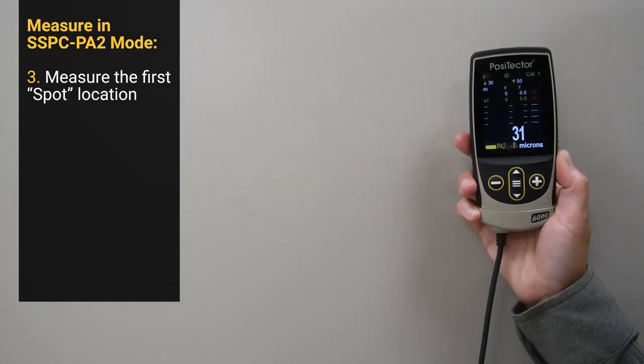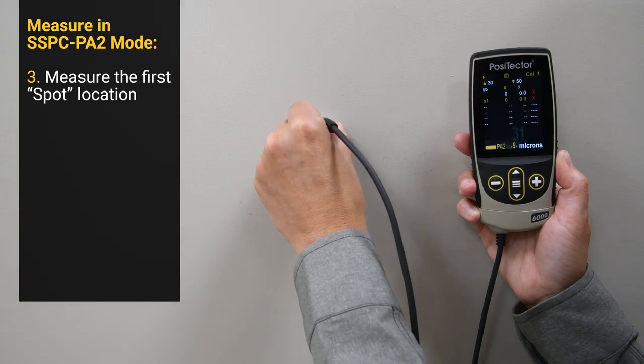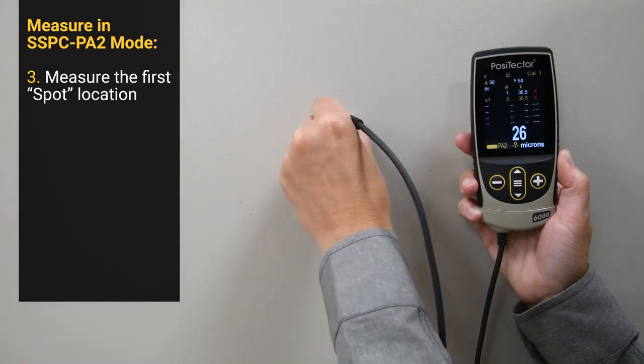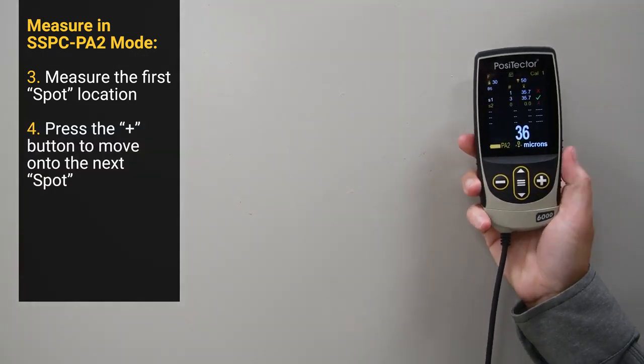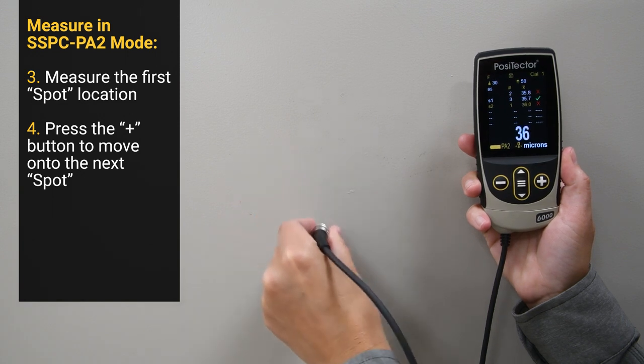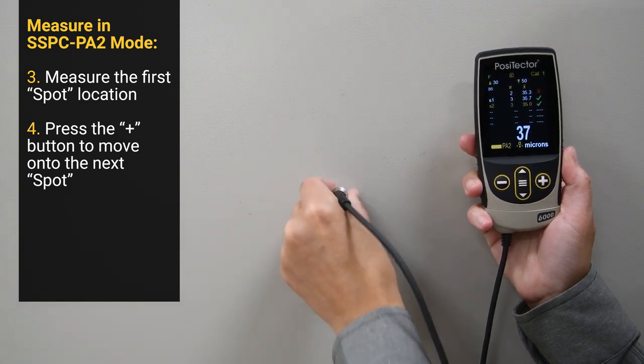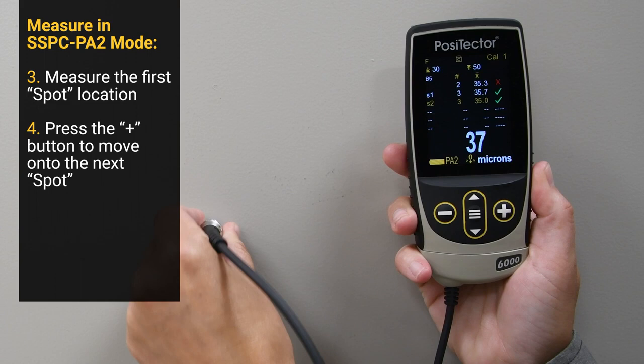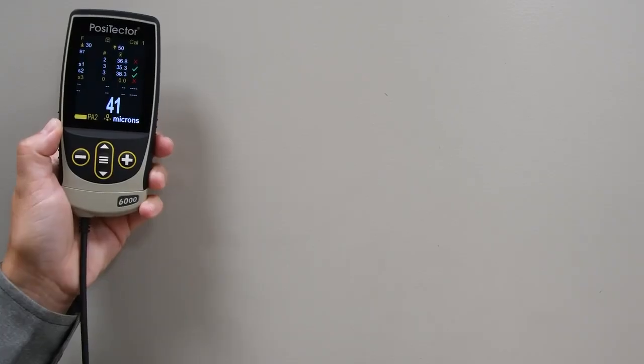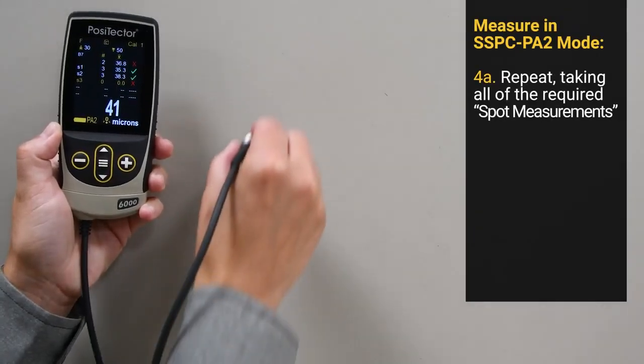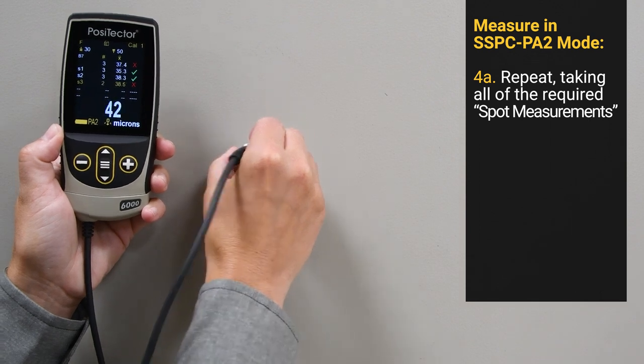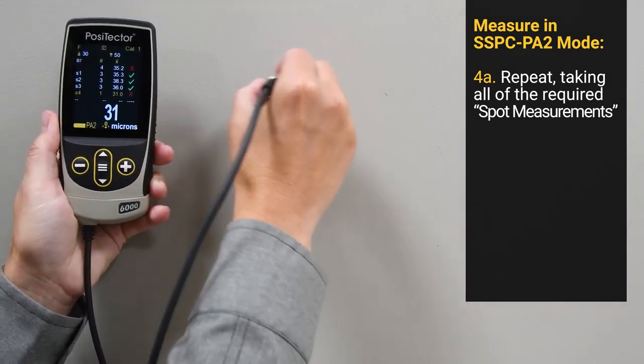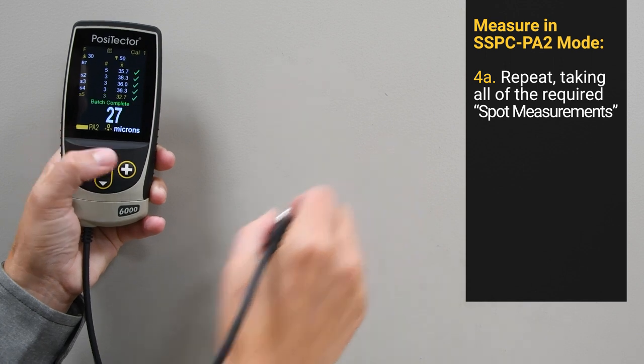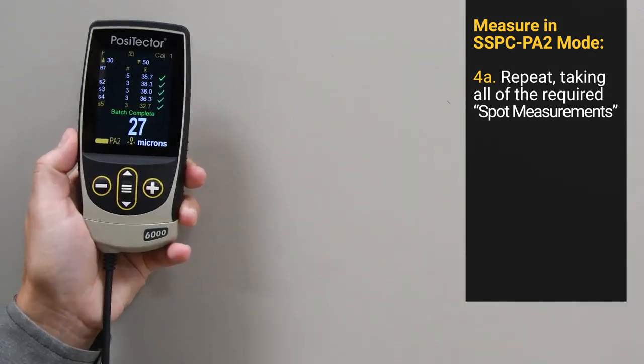Select the first spot location and begin taking measurements. Once the required readings for the first spot are taken, press the plus button to move on to the next spot. A check mark or X will indicate whether the spot measurement passed or failed based on user specifications. Repeat this process until all required spot measurements have been taken. When all of the necessary readings have been taken, a batch complete message will appear.